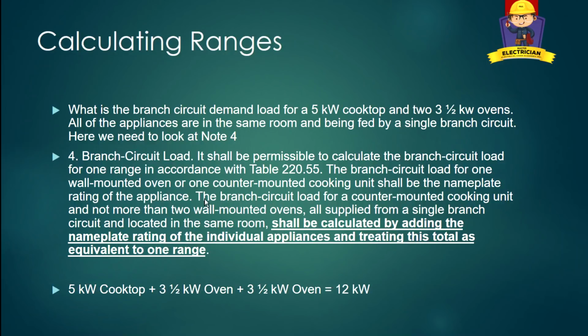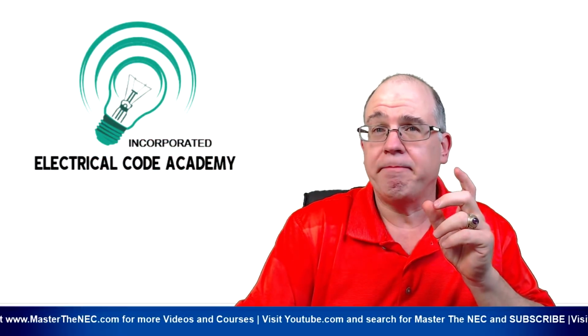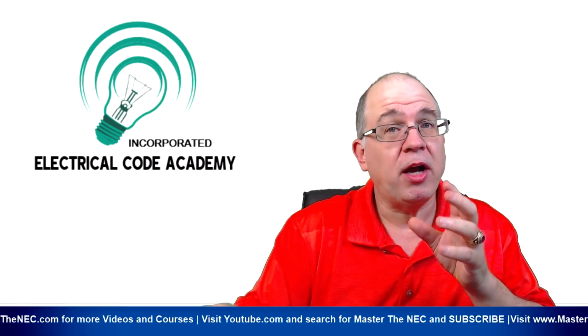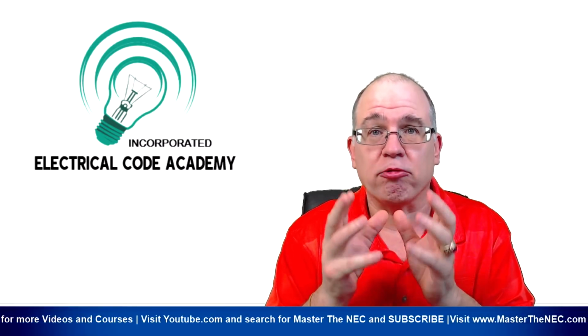Now, here's what it says. The branch circuit load for a counter-mounted cooking unit and not more than two wall-mounted ovens, and that's our example here, all supplied from a single branch circuit located in the same room, which is obviously we're dealing with it all in the kitchen, shall be calculated by adding the nameplate rating of the individual appliances and treating this total as the equivalent of one range. Now, once you do that, or you apply this rule, it now becomes one range. You treat it like a range.